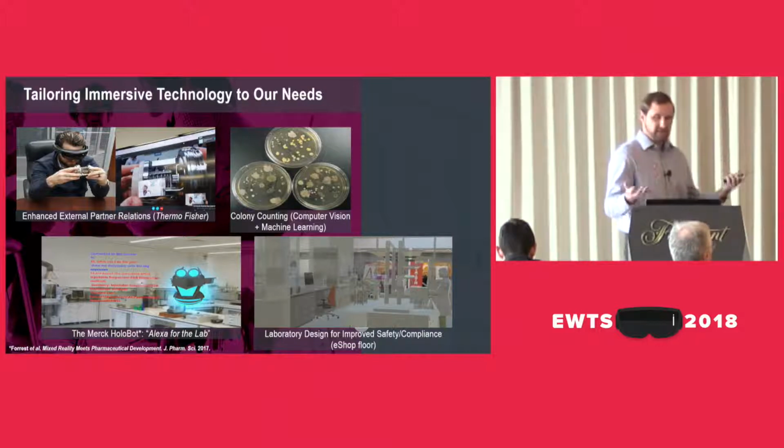And so since you have this expert on demand, you're cutting down on having to schedule a service call, getting the technician out to the site, to basically tell you that you need to clean your source. And it's something that takes 5 minutes. You can cut down. The instrument's up and running, ready to go. We're not losing any time because we have a down instrument.